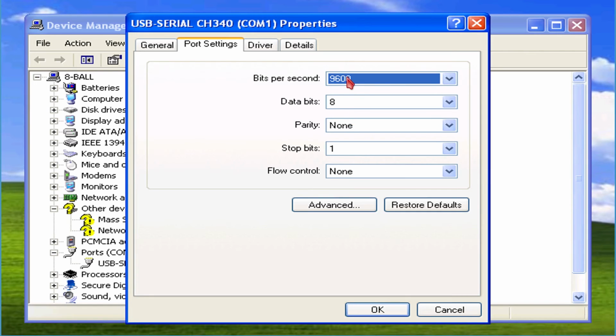In this case the default settings were right, because in order to reset the PDU we need to communicate with it using the standard 9600 baud per second, 8 data bits, no parity bit, 1 stop bit.